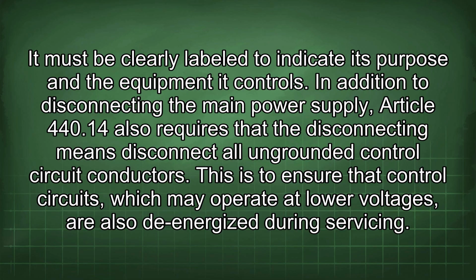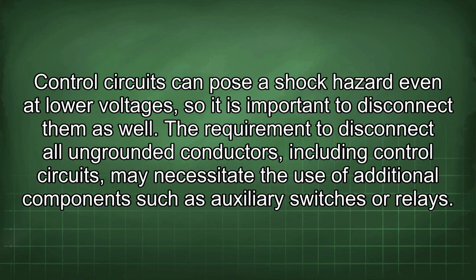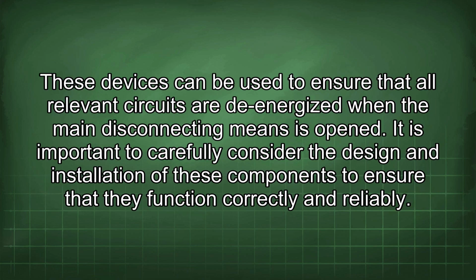In addition to disconnecting the main power supply, Article 440.14 also requires that the disconnecting means disconnect all ungrounded control circuit conductors. This is to ensure that control circuits, which may operate at low voltages, are also de-energized during servicing. Control circuits can pose a shock hazard even at lower voltages, so it is important to disconnect them as well. The requirement to disconnect all ungrounded conductors, including control circuits, may necessitate the use of additional components such as auxiliary switches or relays. These devices can be used to ensure that all relevant circuits are de-energized when the main disconnecting means is opened.